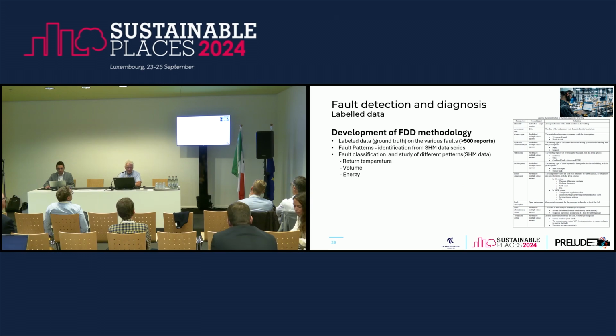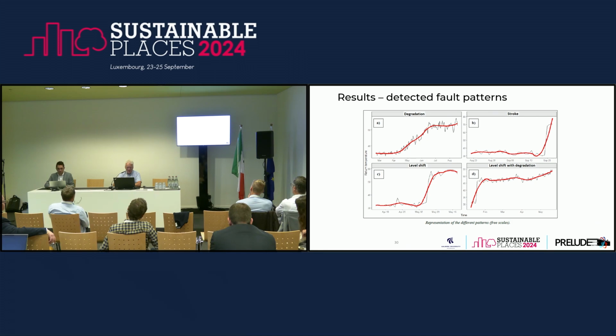We have developed a fault detection and diagnosis methodology for district heating substations, using parameters such as return temperature, volume flow in the substation, and energy use. Based on these fault reports, we tried to identify what the problems are.